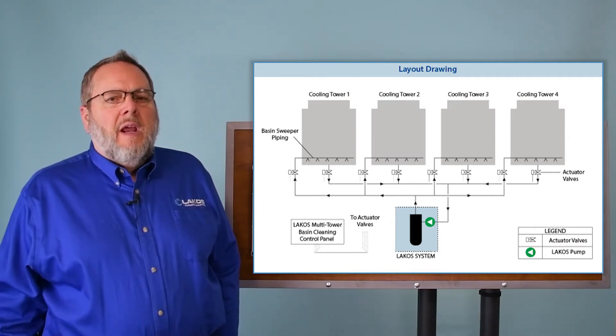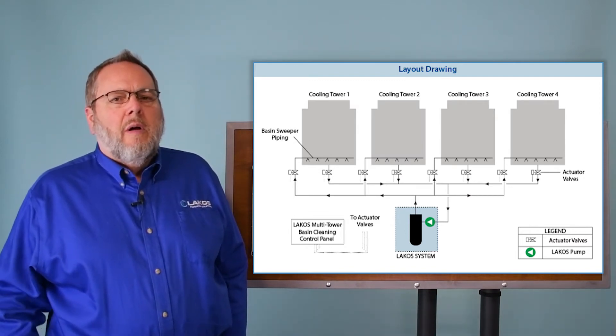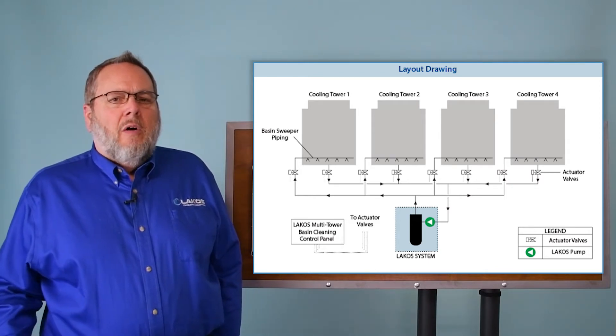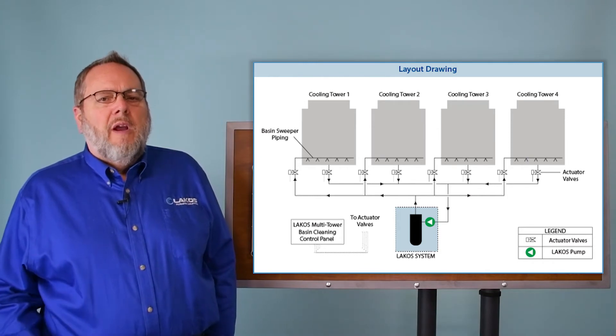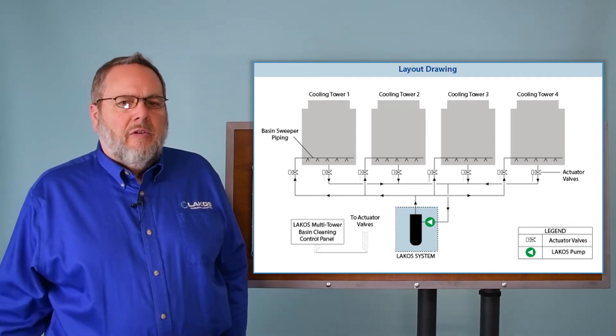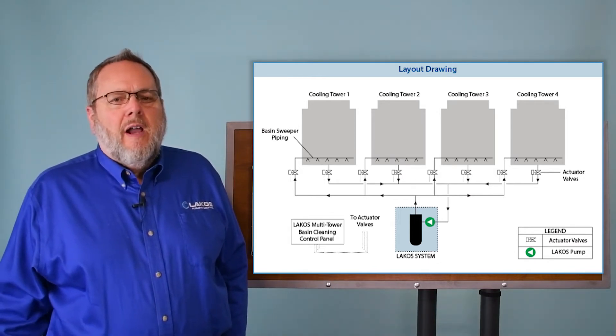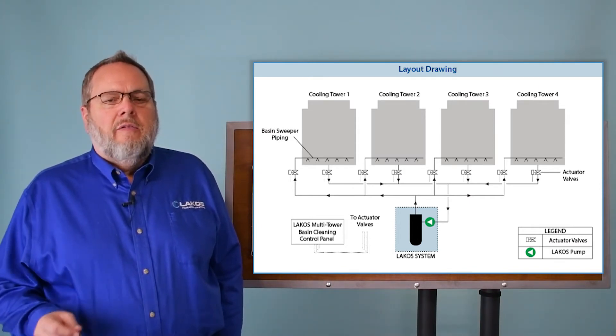It would be only a unit sized for one tower instead of having to size a unit for multiple towers. Also notable is that there is no equalizer line required between all four towers. If you had a single unit sweeping all four towers at once, all four towers would require a connection with an equalizer line. This allows you to use a smaller LAKOS unit once per tower. If you need to take a tower offline, you have the capability to do so without affecting any of the LACOS equipment.